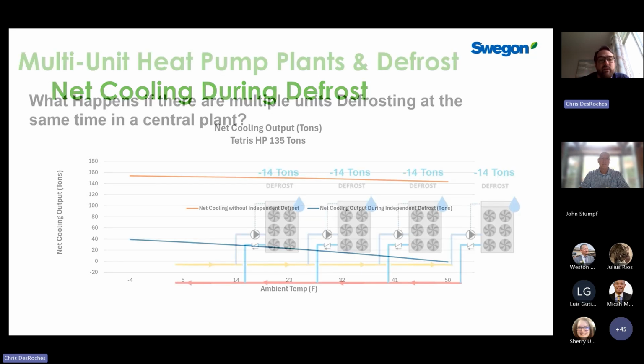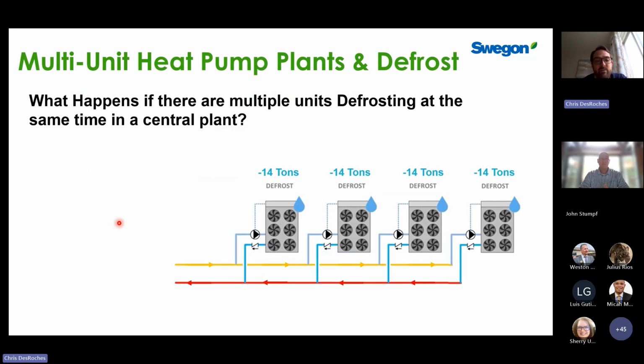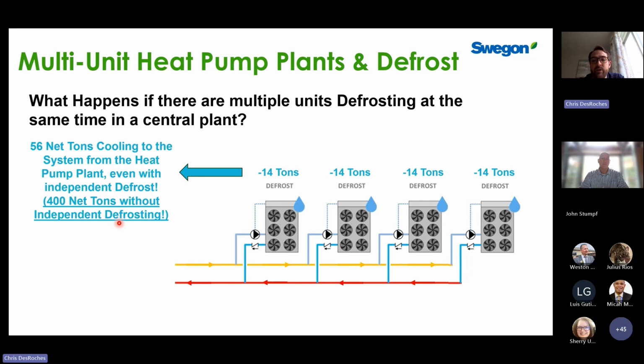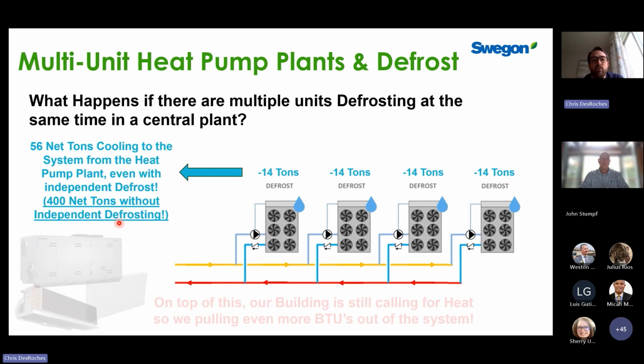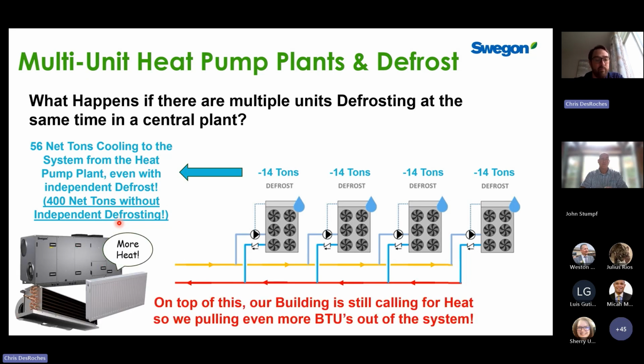But this is even the reason why we need to have generous water volumes in our systems. So what happens if you have 4 units and they defrost at the same time? Even then, we could be pulling out 60 tons of heat from the system. But really the key with a water volume and buffer tank that we have to figure into our calculations as well is we have loads in the building that are connected to the water loop that are still drawing heat. We have air handlers, fan coil units, coils that don't care what water temperature we have going through the system. They just have valves that are opening and asking for more water. So we also need to factor this into our calculation.